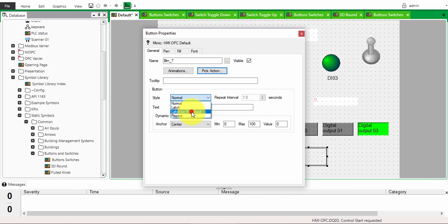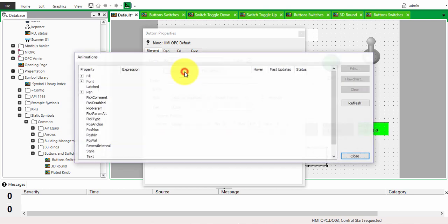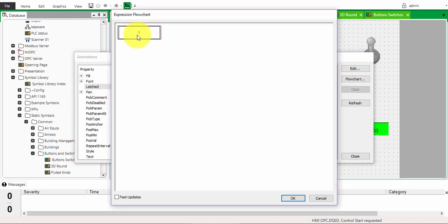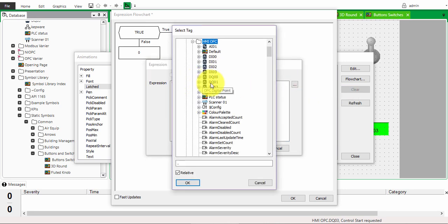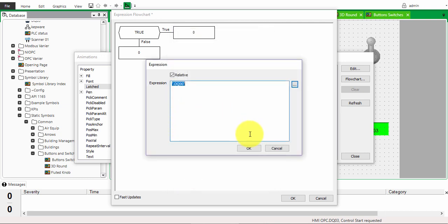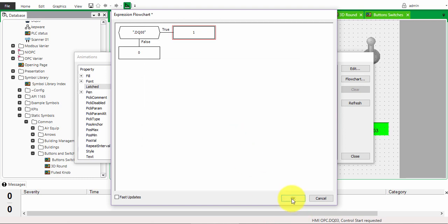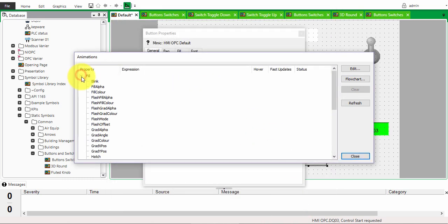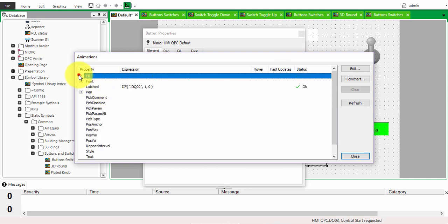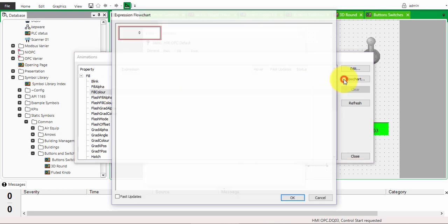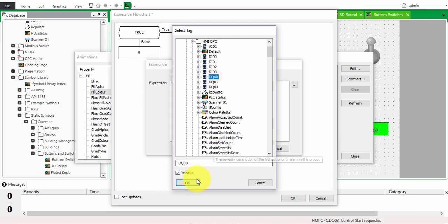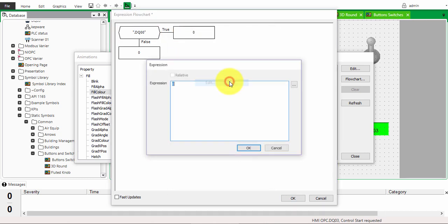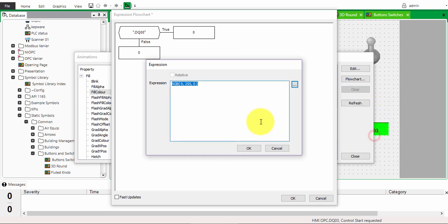Choose 'latch with feedback' — the animation changes faster. To configure, go to animation, then latch, click flow chart, insert, right-click edit, and choose the button you want to control, for example DQ00. Its value when true is 1. To change color, go to fill color, click insert, attach to the same OPC tag, click edit, set green for on.